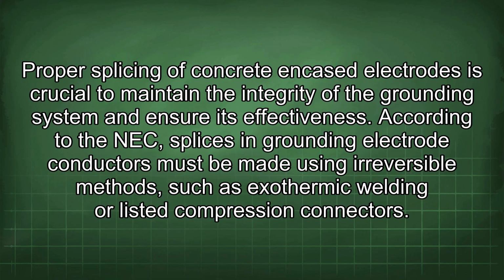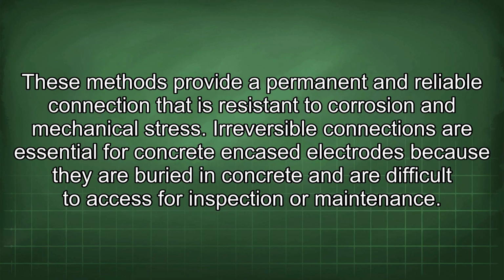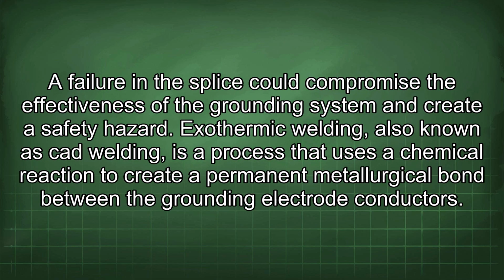Proper splicing of concrete encased electrodes is crucial to maintain the integrity of the grounding system and ensure its effectiveness. According to the NEC, splices in grounding electrode conductors must be made using irreversible methods such as exothermic welding or listed compression connectors. These methods provide a permanent and reliable connection that is resistant to corrosion and mechanical stress. Irreversible connections are essential for concrete encased electrodes because they are buried in concrete and are difficult to access for inspection or maintenance. A failure in the splice could compromise the effectiveness of the grounding system and create a safety hazard.